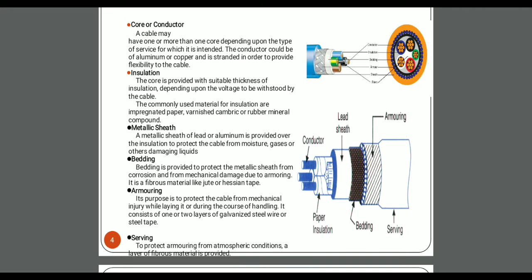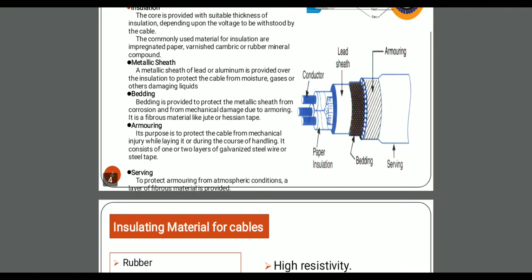The first layer is a conductor, and over the conductor we need to have an insulation, and over the insulation we need to have a metallic sheath, and over that metallic sheath you need to provide bedding, and over that bedding you need to have an armoring and then serving.